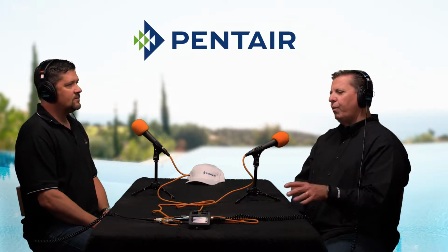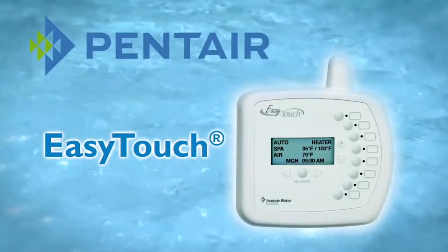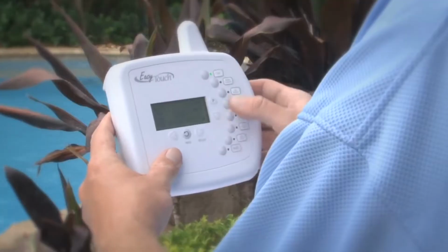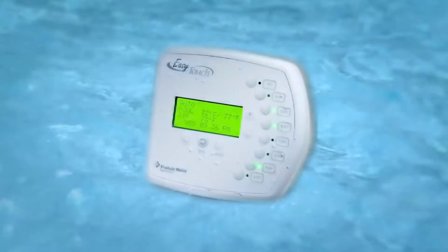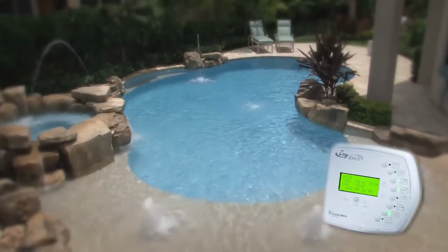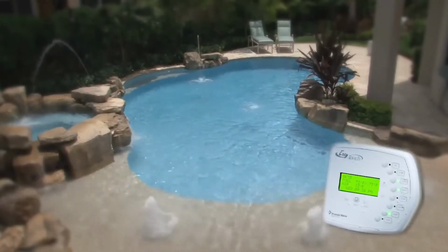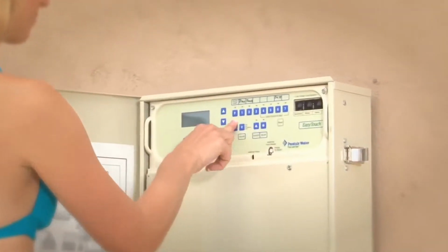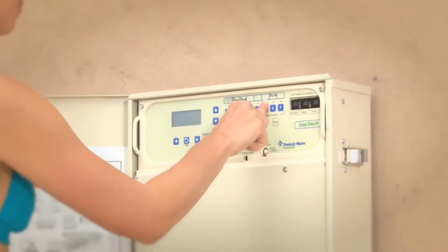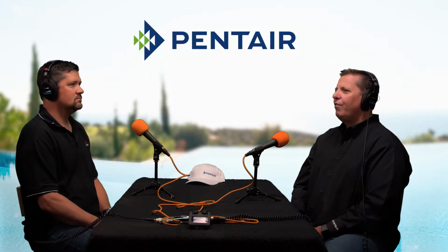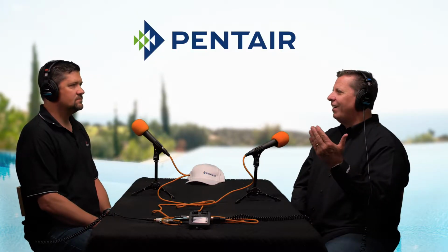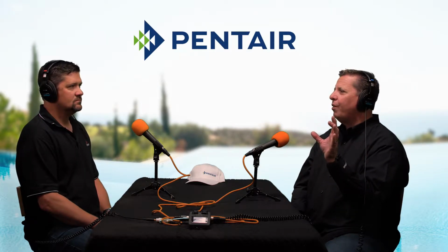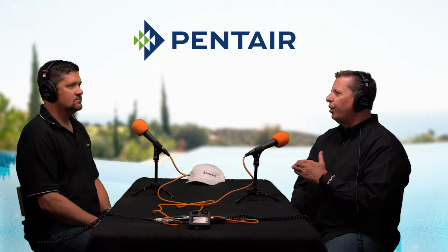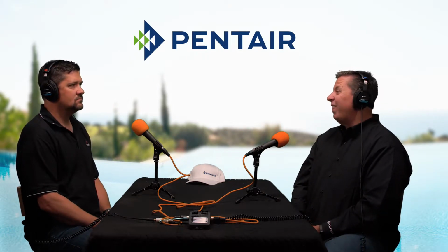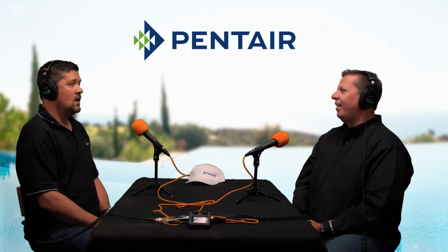So if you look at the automation that we make, an EasyTouch platform will do 2 variable speed pumps. And then we go to the IntelliTouch that has had the ability to do 8 variable speed pumps, or a combination of. The Intellicenter platform gives you the ability to do 16 variable speed pumps. And on jobs like that, sometimes in the past we've made decisions that aren't the best decision for the consumer, but we've had to put single speed pumps in, maybe where we didn't want to, on a water feature, to have the ability to dial it in exactly how the consumer wants it or what the feature needs for the water demand, because we were limited on how many variable speed pumps we could put on there. We think we've overcome that now with having the ability to do 16 and multiple heaters.